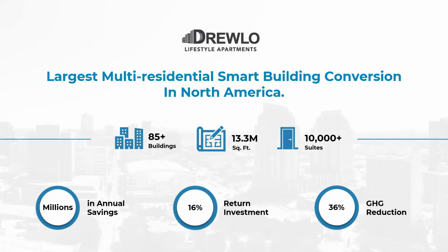I mean, the other one that you can see more specific to multi-res is that a lot of newer multi-res buildings, not Drewlo's, they're still using fan coils, but a lot of newer multi-res buildings are using in-suite water to air heat pumps, supported by a boiler and a cooling tower. So one not full decarb path there, but a partial decarb path is, instead of firing gas to directly heat the hot water, putting a water to water heat pump off of the loop that's already being supported by the boiler and cooling tower. That can offer not just efficiency, but actually in the summertime, when the heat pumps in the suites are in cooling mode, the water to water heat pumps can take that heat from the loop to create domestic hot water before it needs to get rejected to the cooling tower.